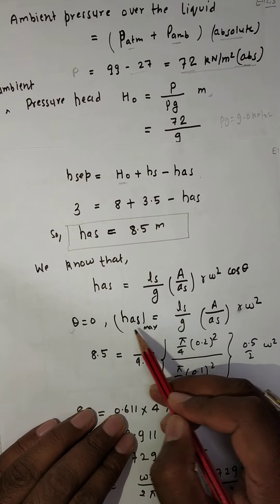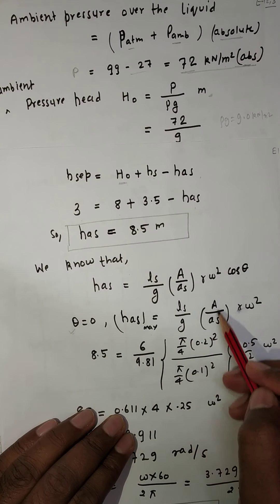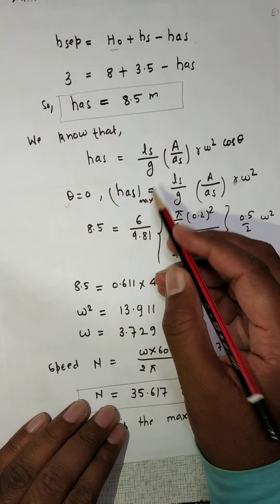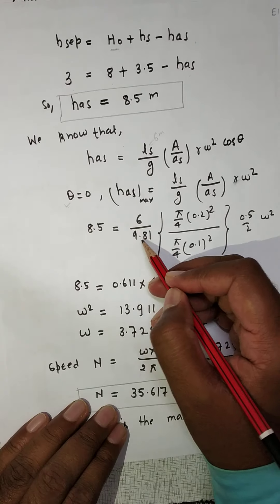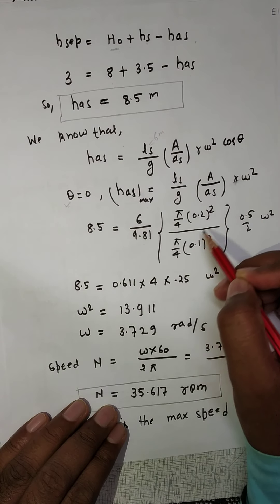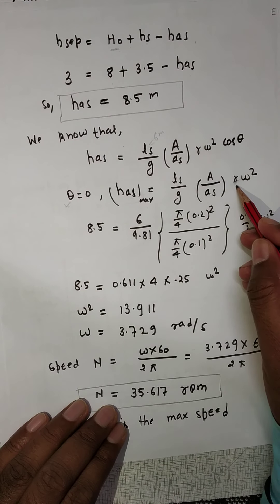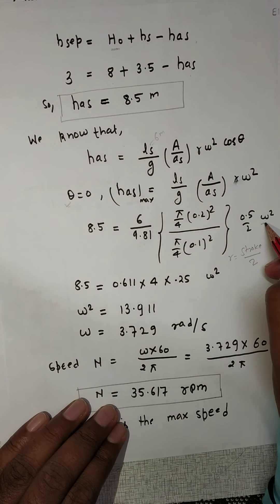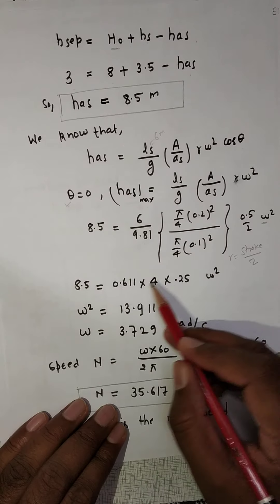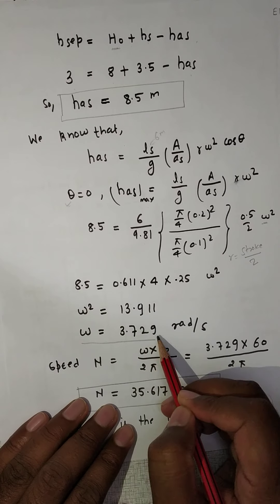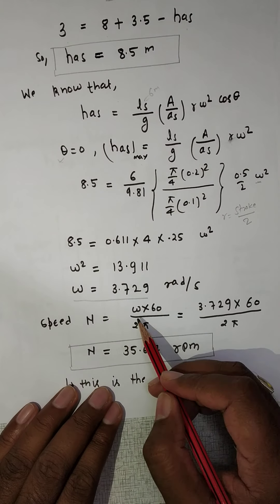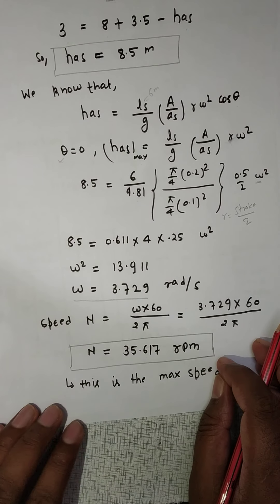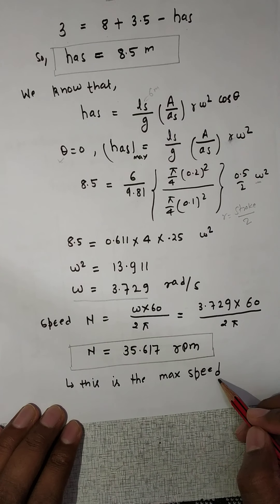For maximum value, θ = 0, so h_s_max = (l_s / g) × (A / A_s) × r × ω². Substituting values: 8.5 = (6 / 9.81) × (A / A_s) × r × ω². The radius r = stroke length / 2 = 0.5 / 2 = 0.25 meters. After calculating with the given cylinder diameter 0.2 m and suction pipe diameter 0.1 m, the value comes out as ω = 3.729 radians per second. Converting to RPM: speed = ω × 60 / (2π) = 35.617 RPM. This is the maximum admissible speed.